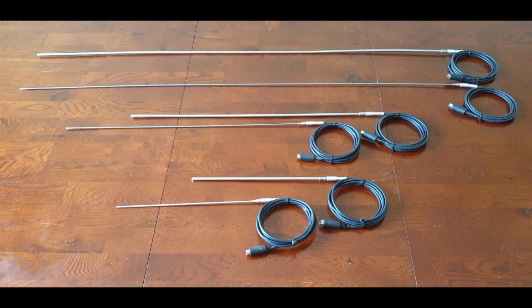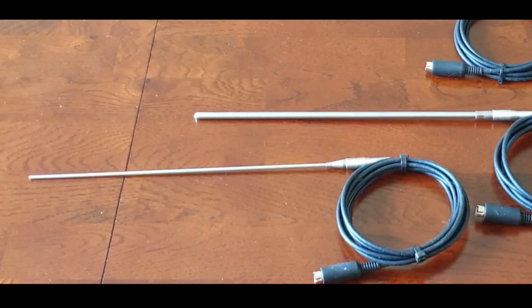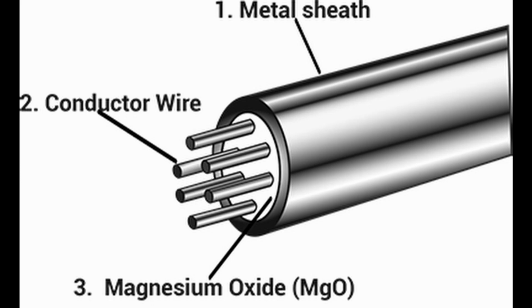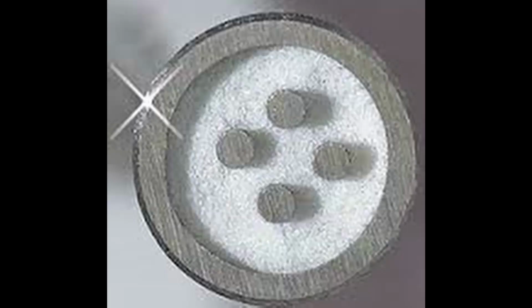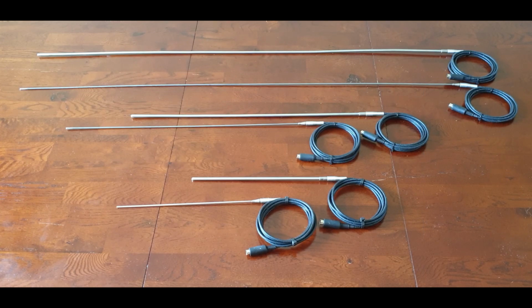In terms of the construction of the mineral insulated PT100 platinum resistance probes, it consists of an outer metal sheath housing the PT100 element and the conductors, which are embedded in a highly compacted magnesium oxide powder. This construction allows the sheath to be bent or formed to shape as required by the user, but remain rigid during use. The whole assembly is hermetically sealed, giving the conductors full protection from the operating environment.